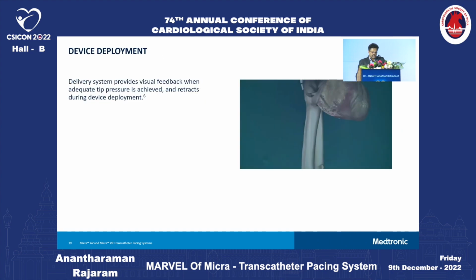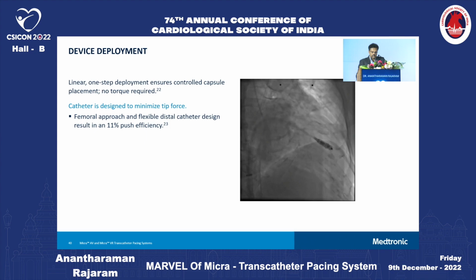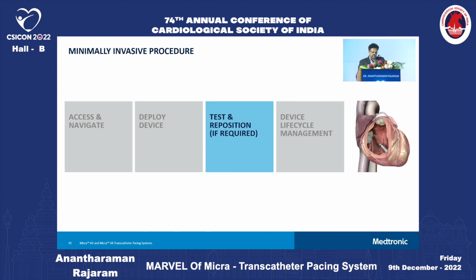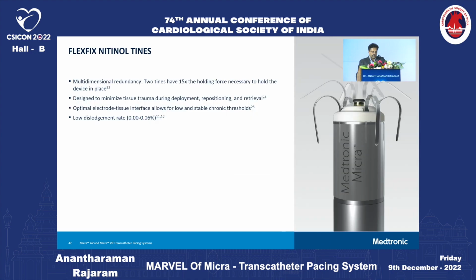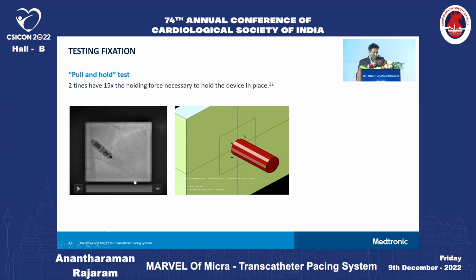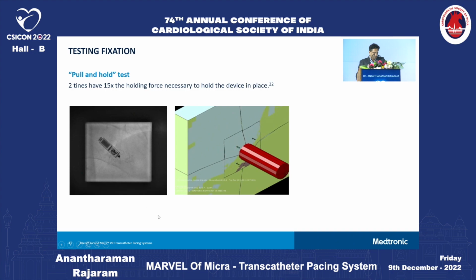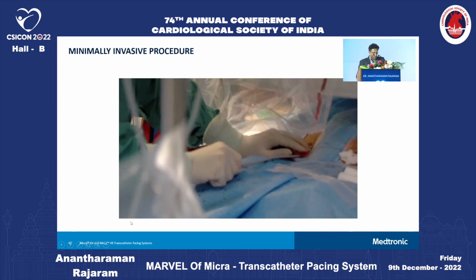And once that is confirmed, once the contact is there, you deploy it half, and then release the tension in the catheter, and then lock it. So there are 4 tines, if 2 of them hold, that's more than enough. It gives 15 times the holding force necessary. If you get 3, that's better. If you get all 4 tines holding, that's the best. But anything around 2 is fine. So you can do the tethering test once the pacemaker is in place.